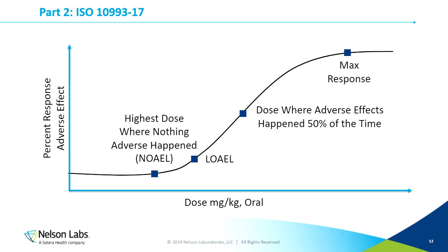Ideally, what the toxicologist wants to find is an animal study that has relevant data, meaning a relevant route of exposure to how the device is used, as well as a relevant duration of exposure. So for example, if you have devices like pre-filled syringes and it's going to be a single exposure, it might be overkill to be looking at 2-year animal studies for critical effects.